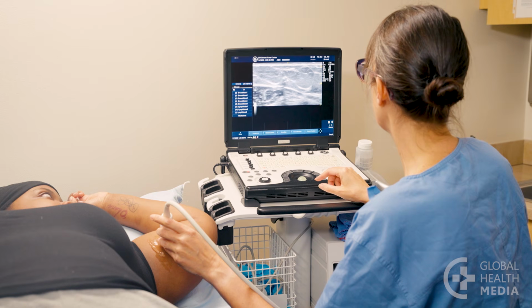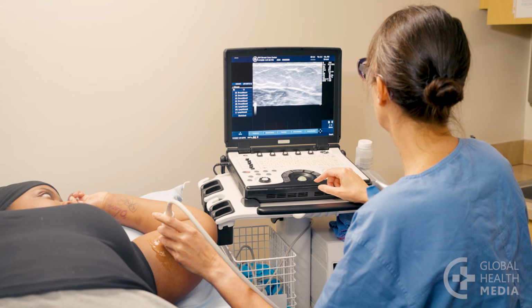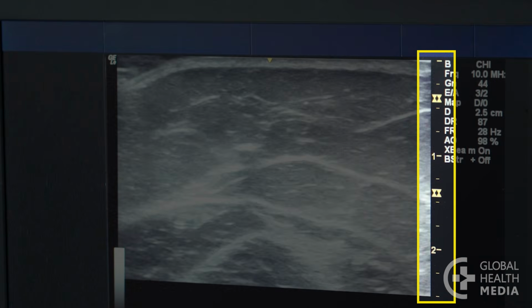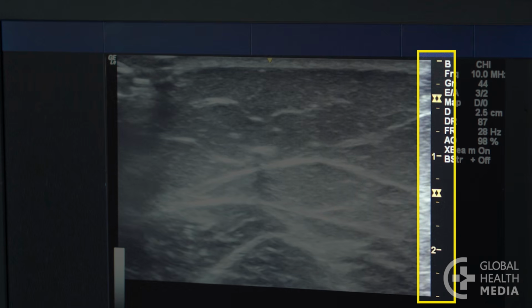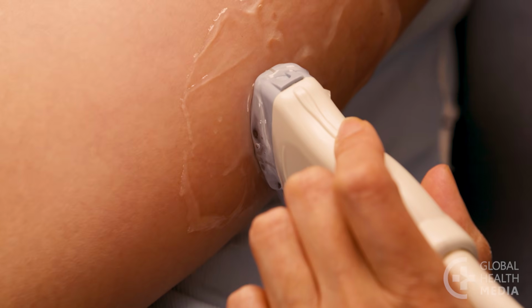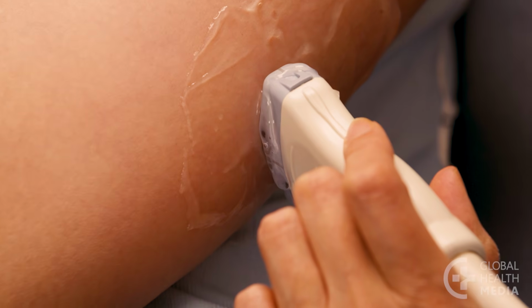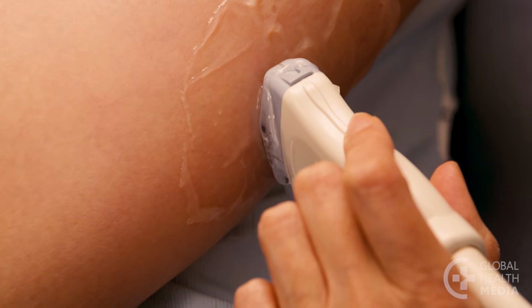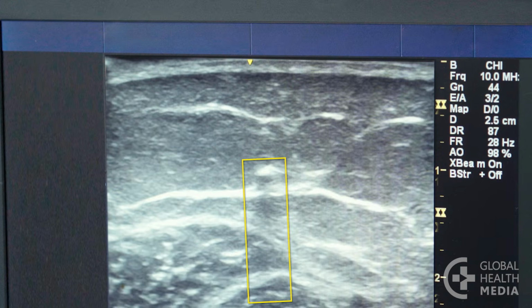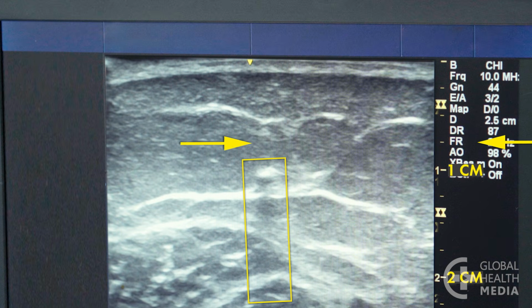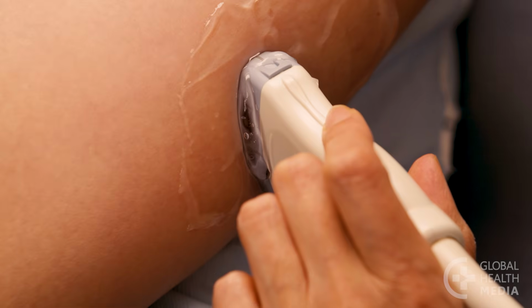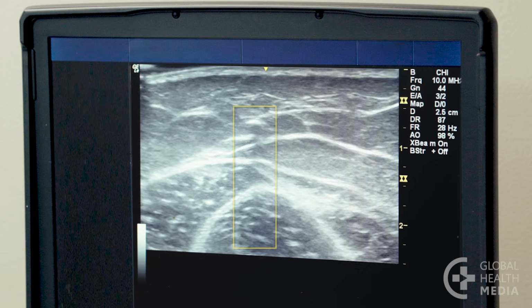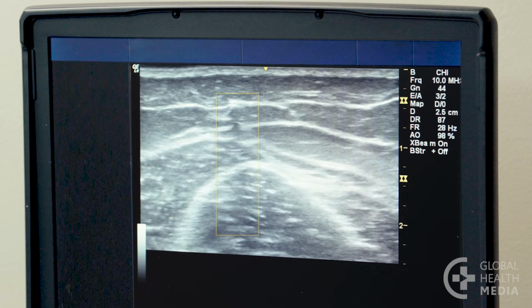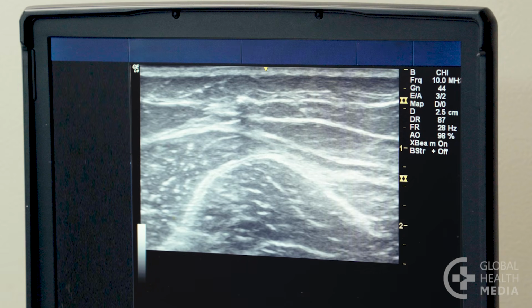Next, measure the depth of the implant. The markings here show the depth in centimeters. Be sure to hold the probe lightly to avoid compressing the tissue. The implant is 1 centimeter below the skin surface. Compressing the tissue will make the implant appear more shallow than it actually is.